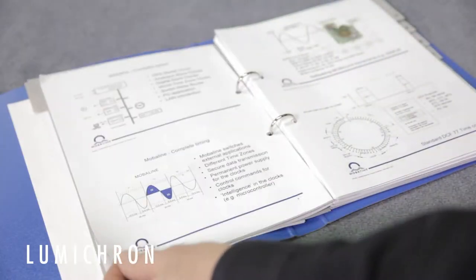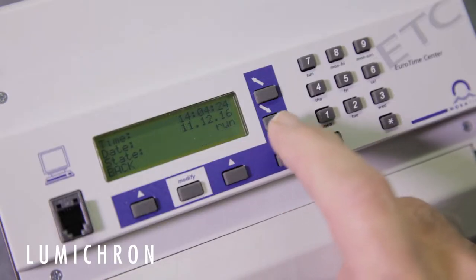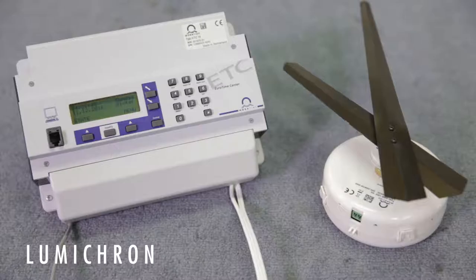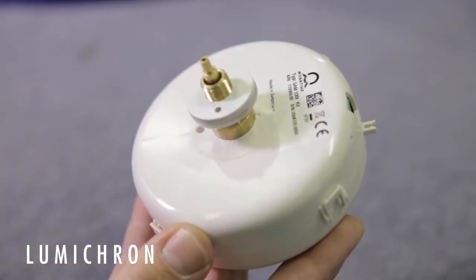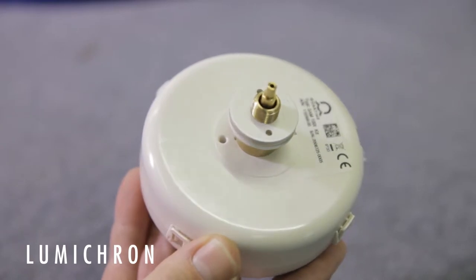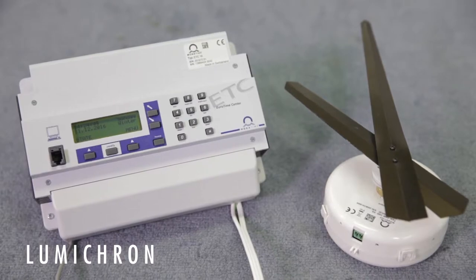The master clock controller outputs a time code called Mobaline. At about 18 volts, it delivers the power and time code for a MOBATIME clock movement, such as this SEM100 model. The clock movement reads the signal and will automatically set to the proper time as indicated in the controller.